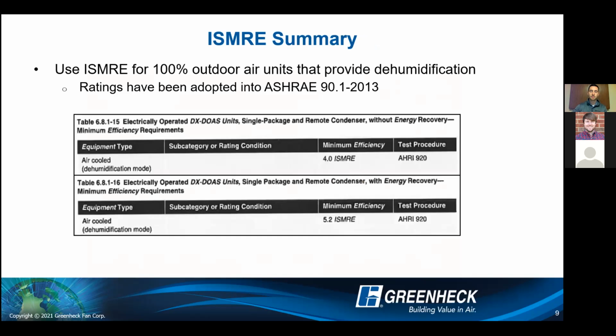So hopefully that makes some more sense as to why you will see ISMRE versus that IEER value in submittal packages. So real quick, Jake, there is a question specific to that. Do any energy codes require ISMRE to be used in lieu of IEER? So that's a really good question. And actually, they're still working on it, and it's going to continue to be adopted. But you can see ASHRAE 90.1 in this screenshot. Those ISMRE ratings have already been adopted in 2013. I believe the last time I looked at the Georgia area, it was on the 2007 version of ASHRAE 90.1.